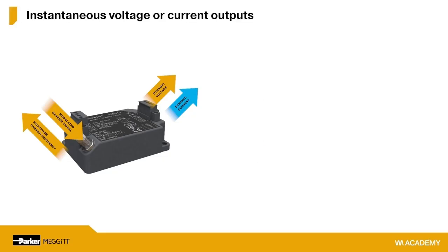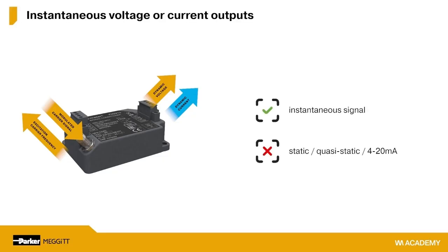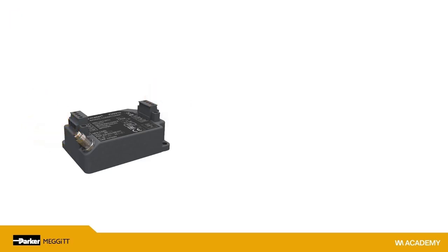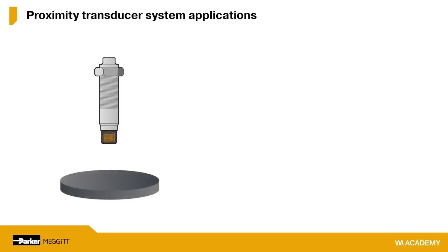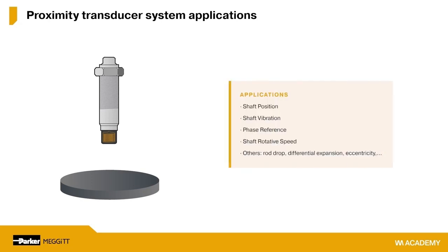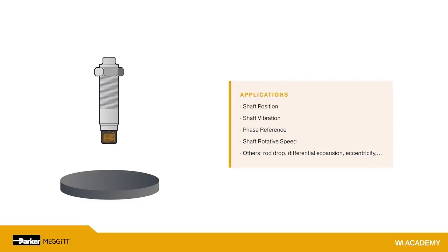It's important to remember that these are instantaneous voltage or current outputs and not static or quasi-static signals, such as from 4 to 20 milliamp process transmitters. We can therefore obtain a true instantaneous waveform output from a proximity transducer system, making it useful not only for shaft position, but as well for shaft vibration, for phase reference, for shaft rotating speed, and for many other measurements.